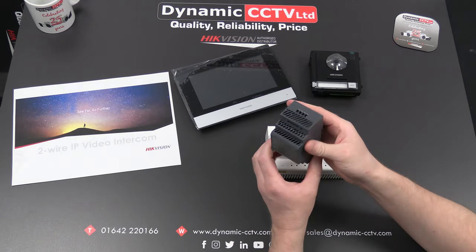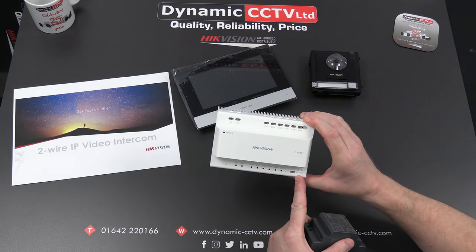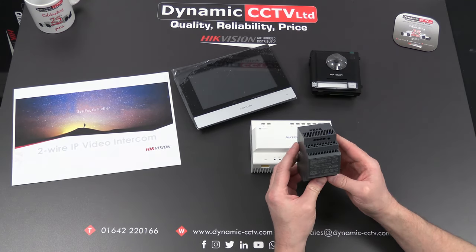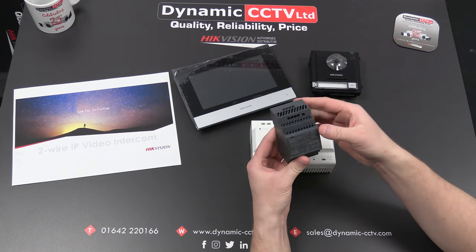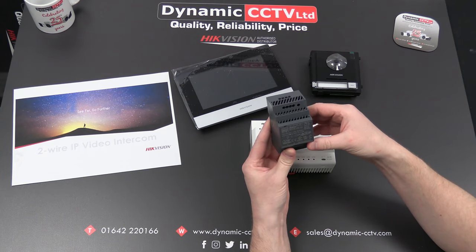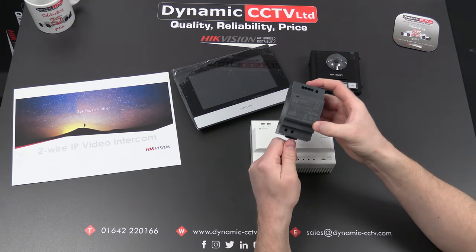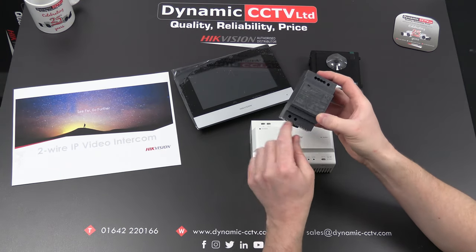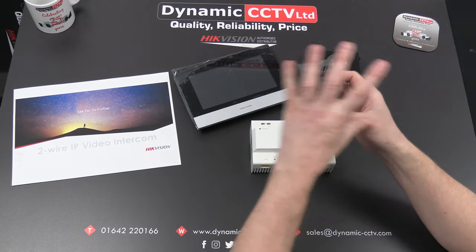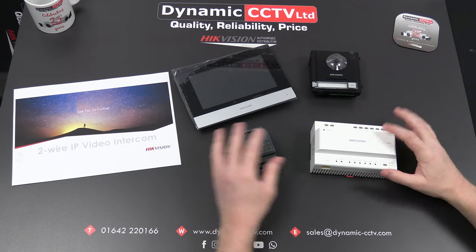This device is the PSU — it powers the controller and connects via a 24-volt DC input. The model is DS-KAW60-2N and it has a DIN rail connection on the back. It's designed to be installed inside electrical consumer units or electrically safe enclosures, as the mains connections at the bottom have limited electrical protection. Installing it within a consumer unit or electrically safe enclosure is strongly recommended.